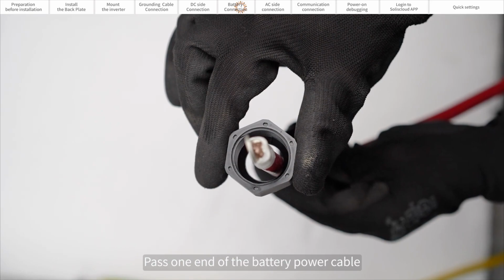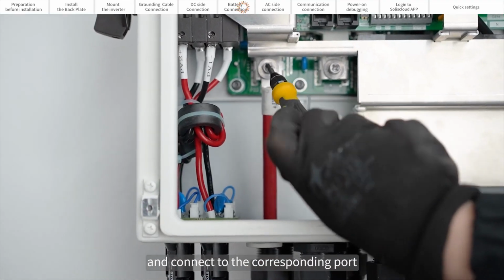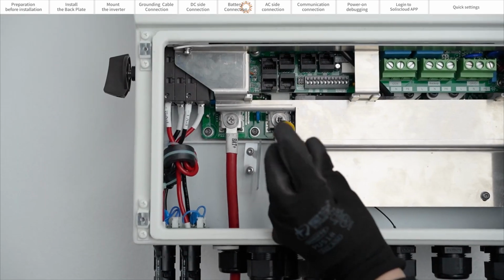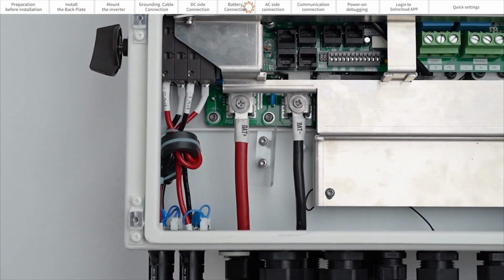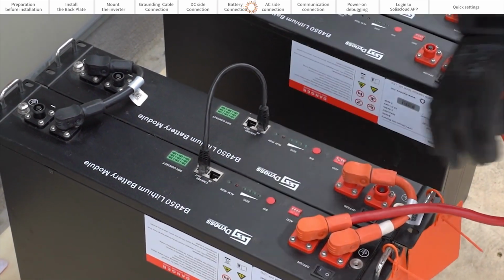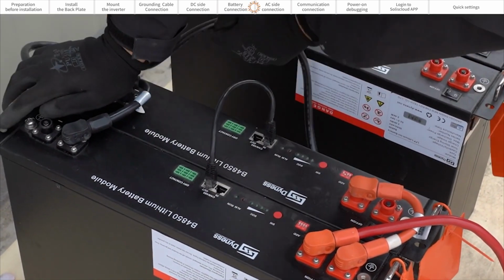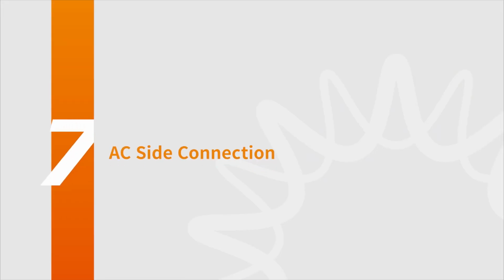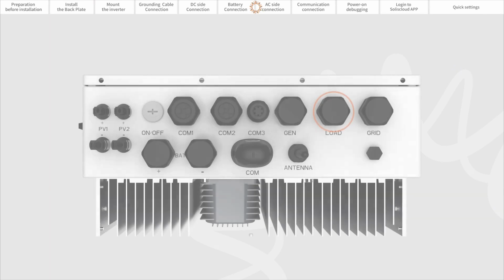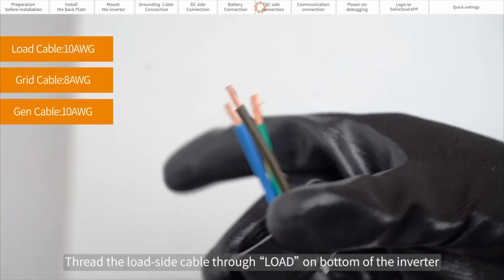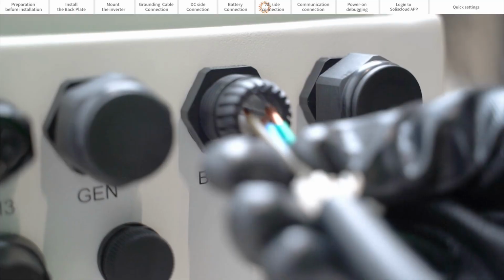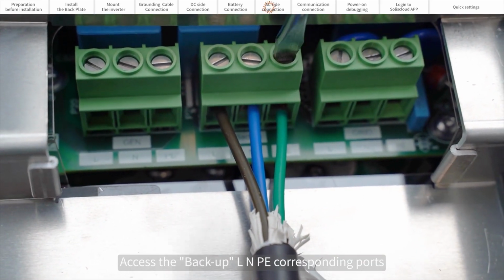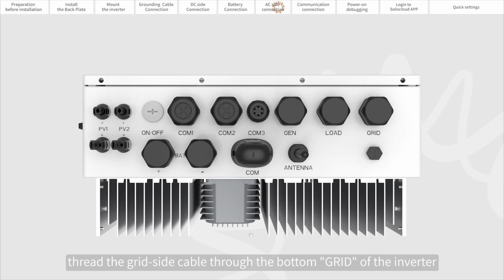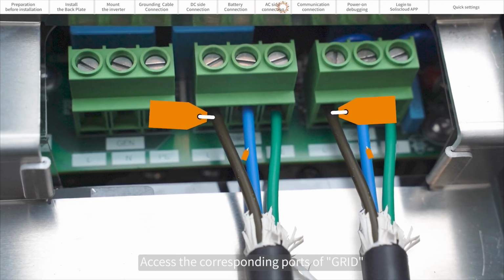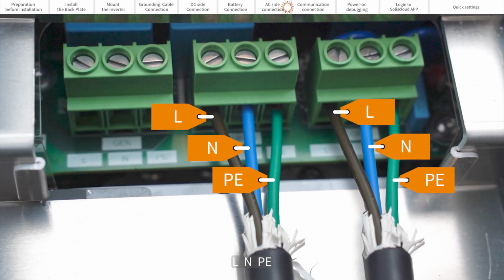Pass one end of the battery power cable through the BAT port at the bottom of the inverter and connect it to the corresponding port. The other end is connected to the battery. Part 7. AC side connection. Thread the load side cable through the LOAD port on the bottom of the inverter, and access the backup line, neutral, and earth corresponding ports. Similarly, thread the grid side cable through the GRID port at the bottom of the inverter and access the corresponding ports of the grid line, neutral, and earth.